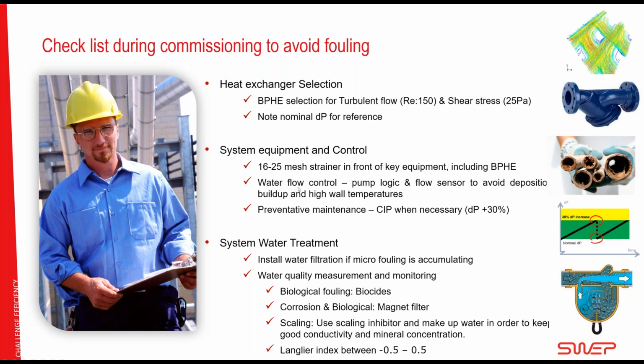Make sure that you know your flow. If you have a flow, make sure that you verify it. Have a flow sensor or a smart pump to make sure that you have the flow that you think you have. Keep an eye on the system. If the pressure drop over the system increases more than 30% from your reference point, you probably need to do something about it. Cleaning in place could be necessary.